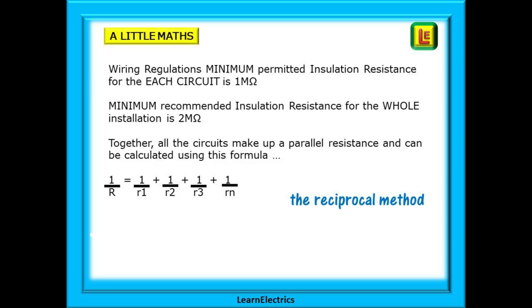We need to look at some simple maths now. This is basic Ohm's law and is easily followed. The wiring regulations tell us that the minimum permitted insulation resistance for each circuit is one megaohm — one million ohms. But the minimum recommended insulation resistance for the whole installation is two megaohms — two million ohms. Together all the circuits make up a parallel resistance, and this can be calculated using the formula: 1/R = 1/R1 + 1/R2 + 1/R3 + 1/Rn and so on.